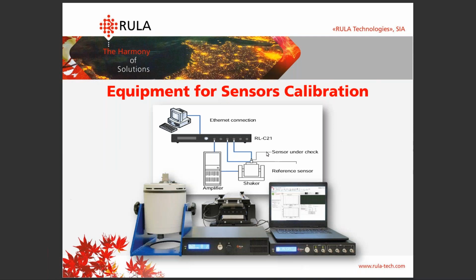Now let's cover very briefly the equipment you're going to need for sensor or accelerometer calibration. You can see the controller that I've just mentioned down there, and on top there is a PC with a pre-installed TestUp software calibration module. Then we have a shaker. Could be a specific model shaker or a small shaker for calibration. There's a range of brands that you can use. And then in the center of the picture, you can see our RULA 200. It's a power amplifier with 200 VA power output, ideal for calibration purposes.